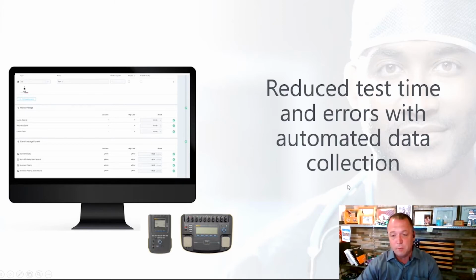My point is, when recording the values, any of our Fluke devices—specifically our ESAs, our electrical safety analyzers, and our defib analyzers—if we're doing the test and it fails, it's going to bring all that data right into OneQA. So if you have a failed test result, it's going to be marked as a failed test result, and it's going to force that technician to do something about that piece of equipment.